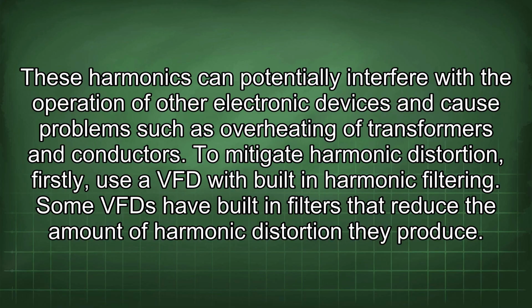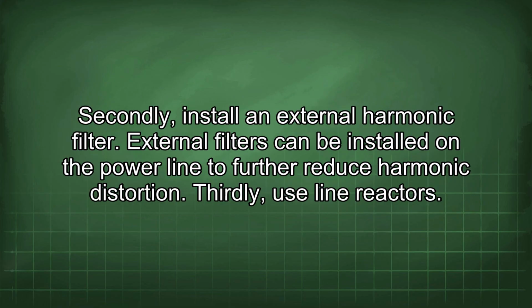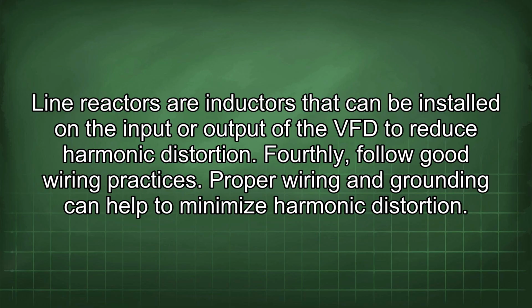Some VFD have built-in filters that reduce the amount of harmonic distortion they produce. Secondly, install an external harmonic filter. External filters can be installed on the power line to further reduce harmonic distortion. Thirdly, use line reactors. Line reactors are inductors that can be installed on the input or output of the VFD to reduce harmonic distortion. Fourthly, follow good wiring practices. Proper wiring and grounding can help to minimize harmonic distortion.